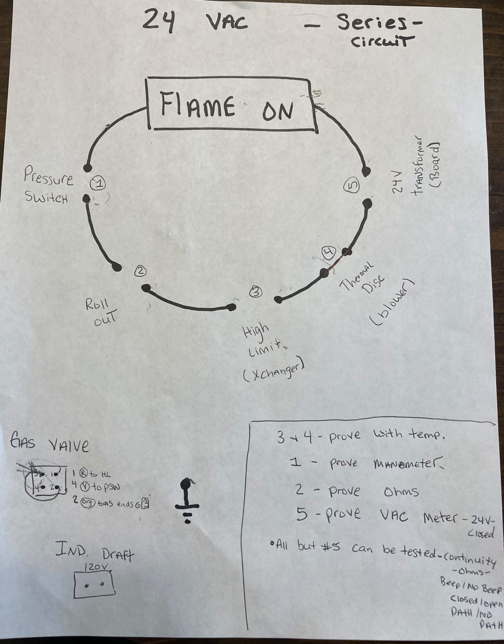We want to test it right where you're at. Do you have 24 volts going to it? Do you have 24 volts coming past it? Or do you not? Or you could pull the leads off of it and test for continuity. Beep or no beep. Is there a path or is there not a path?